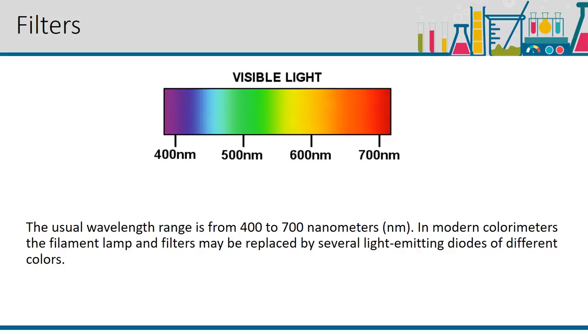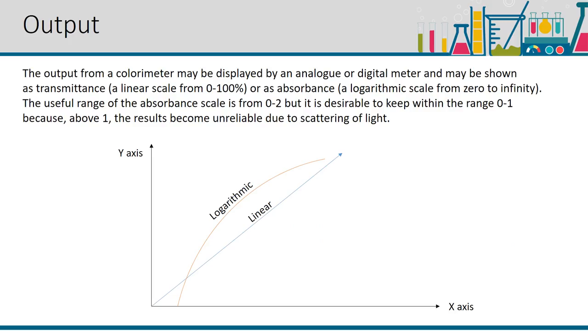The output from a colorimeter may be displayed by an analog or digital meter and may be shown as transmittance, a linear scale from 0 to 100 percent, or as absorbance, a logarithmic scale from 0 to infinity. The useful range of the absorbance scale is from 0 to 2, but it is desirable to keep within the range 0 to 1 because above 1, the results become unreliable due to the scattering of light.